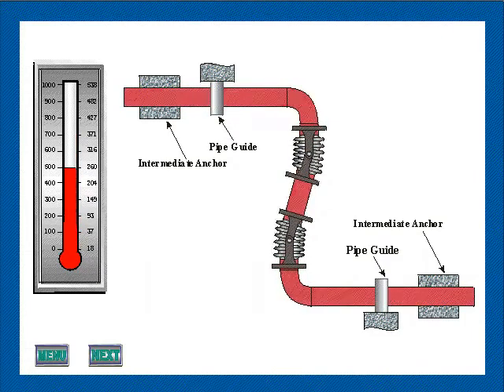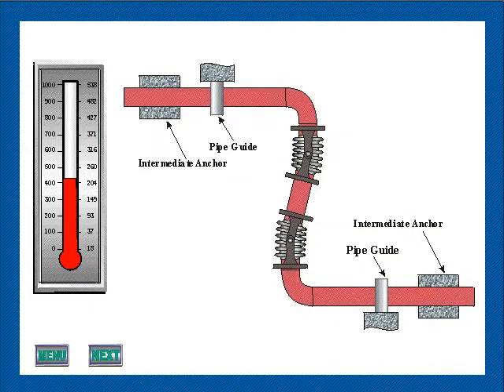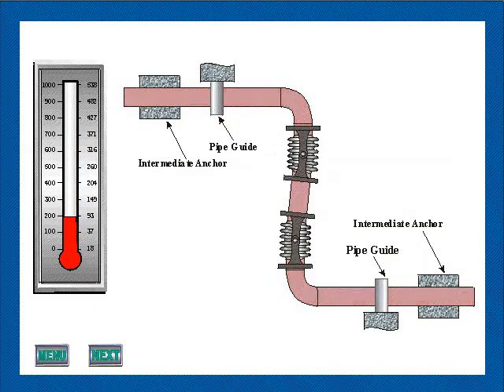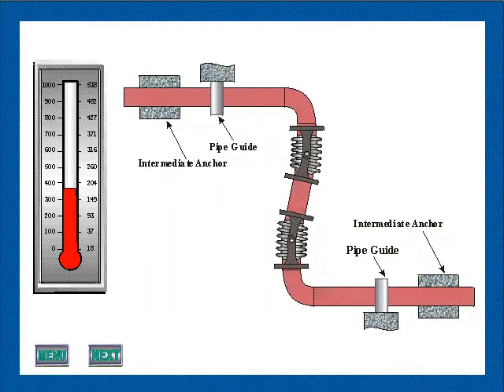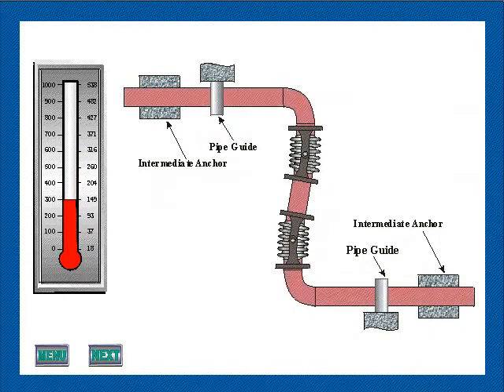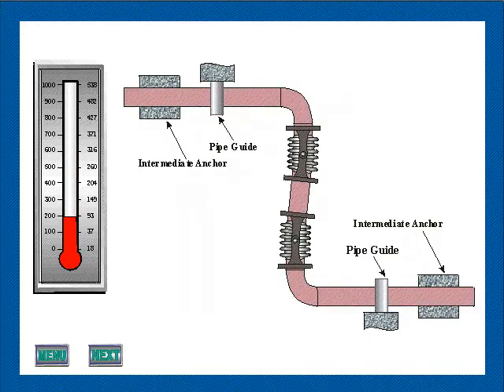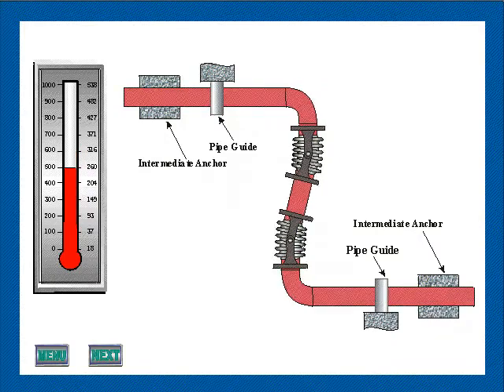Where one long leg is sufficiently flexible to absorb the full thermal growth of the offset leg, the other long leg may be controlled to permit longitudinal movement only. The planar guides shown at the ends of the long piping runs near the elbows are intended to maintain the plane of the piping system only and must allow for the bending deflections of the long piping legs.